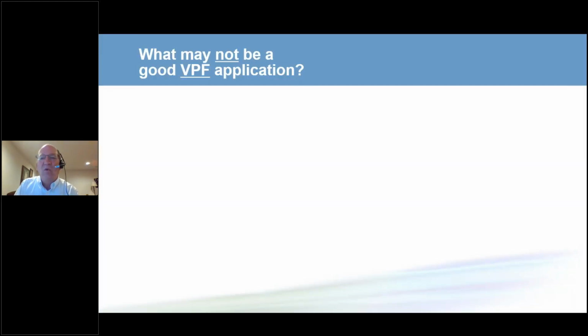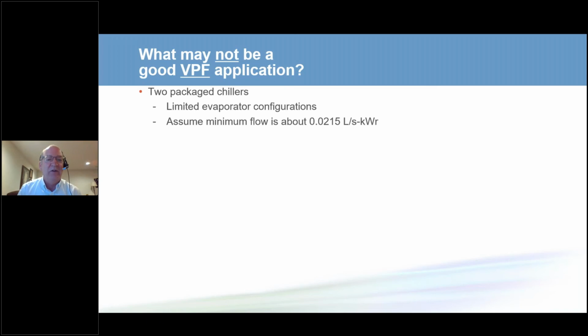One thing we like to share when we give presentations is what is not a good variable primary flow application. This is, we have 2 package chillers. I kind of separate chillers into 2 different categories. One is centrifugal chillers, which are customized; the chiller is chosen for the job. The scroll and screw chillers are more manufactured, and therefore chiller providers have fewer options. They're more packaged, is what we call them.